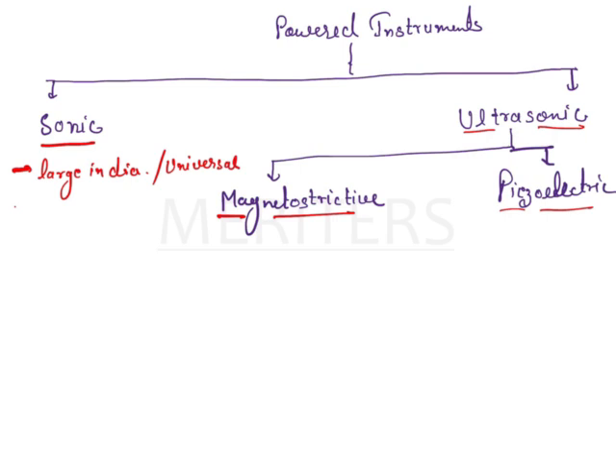The tip has an orbital type of vibrating action. Sonic and ultrasonic instruments work on vibration, and here the vibration is basically orbital type. The vibration range for sonic instruments is around 2,000 to 6,500 cycles per second. These are the important points about the sonic instrument.